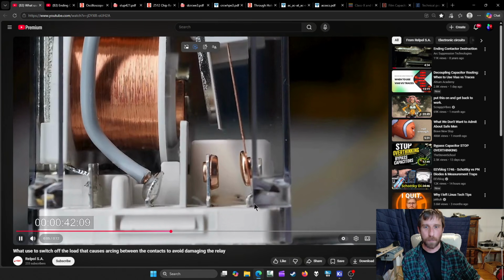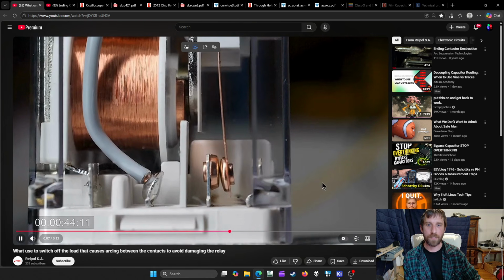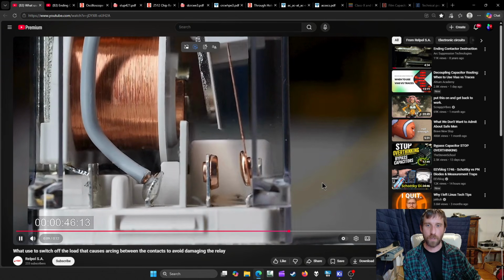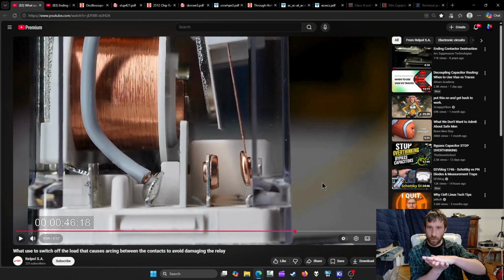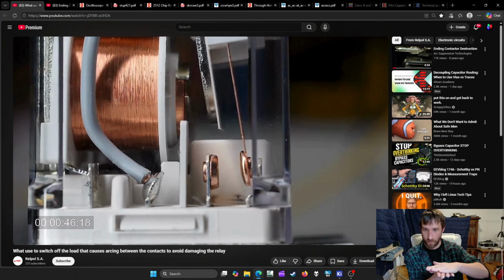As you can see here, some arcing happening. Over time, this will mess up your relay contacts to the point where they'll either weld together, so your device will never turn off, or so much material will be lost on the contacts that they don't make an electrical connection, in which case your device doesn't turn on. So a little more dramatic example with this.